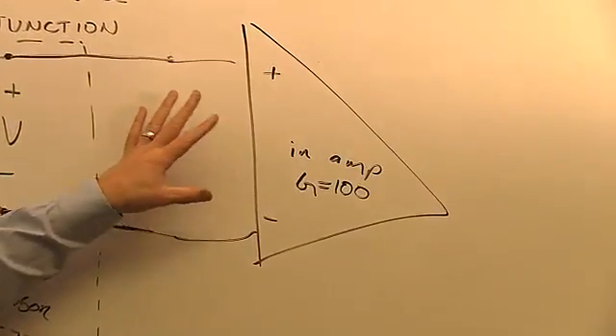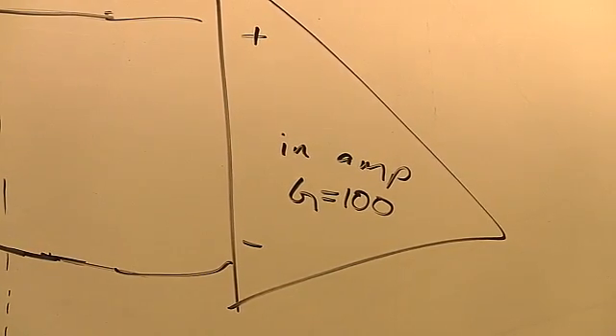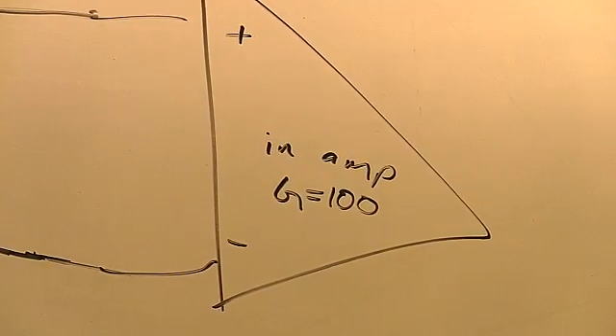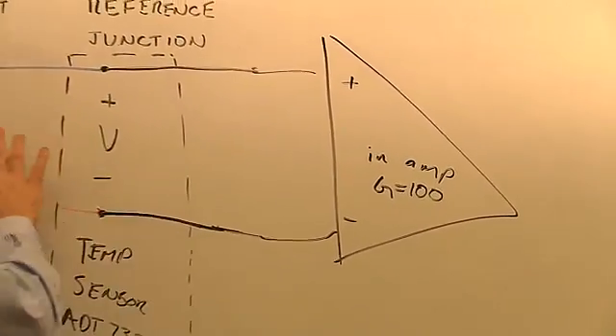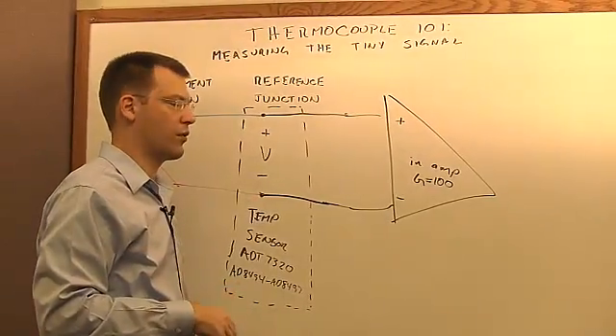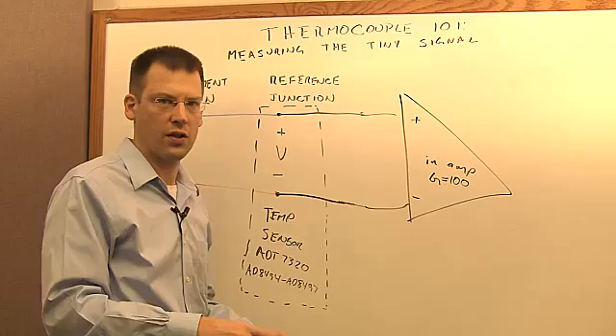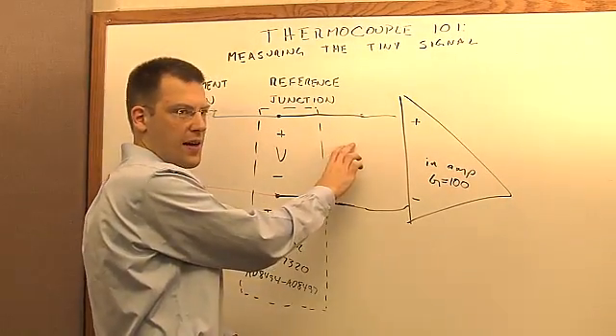The reason that we use an instrumentation amplifier instead of, say, an op amp is that it gives us differential magnification capability. We may pick up some common mode noise on this thermocouple, and if we just measured single-ended, that common mode noise would contribute to our signal and it would be hard to distinguish this tiny signal.